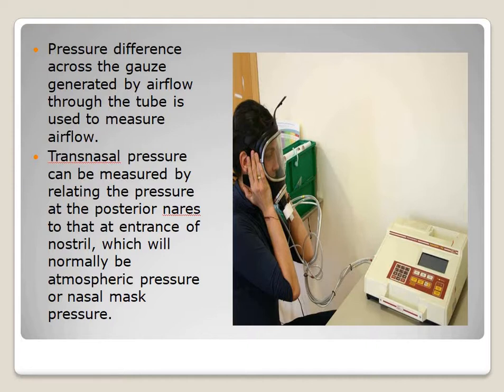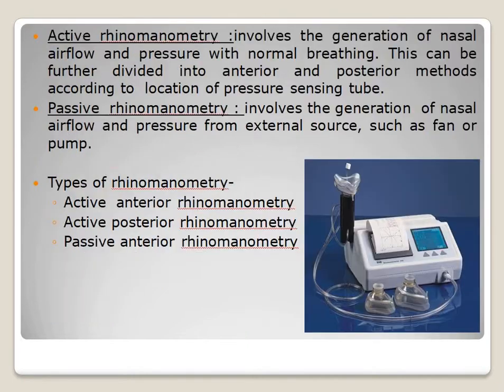Transnasal pressure is measured by relating the pressure at the posterior nares to the entrance of the nostrils, which is normally atmospheric pressure, or the nasal mask pressure. There is active and passive rhinomanometry: in passive rhinomanometry, nasal airflow and pressure are generated from an external source such as a fan or pump, whereas in active rhinomanometry the patient generates the flow by normal breathing. This is further divided into anterior and posterior methods according to the location of the pressure sensing tube.